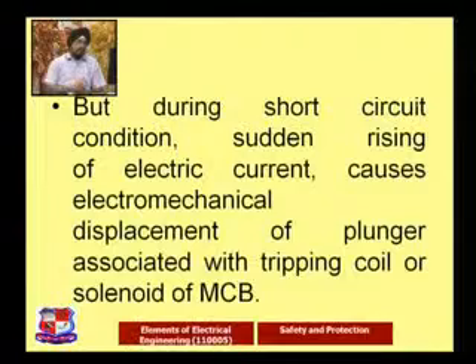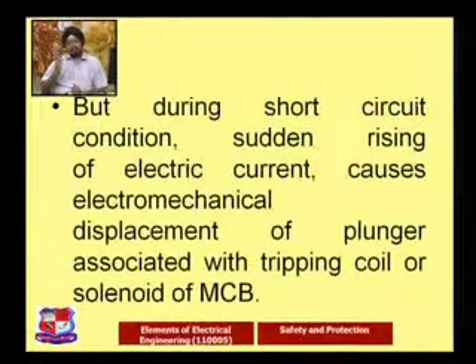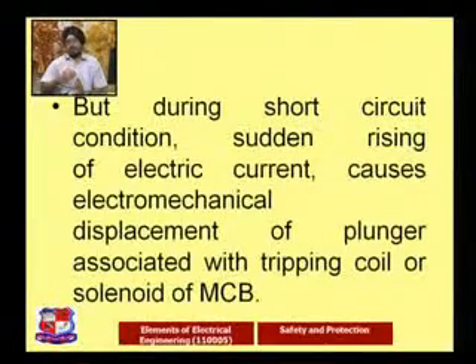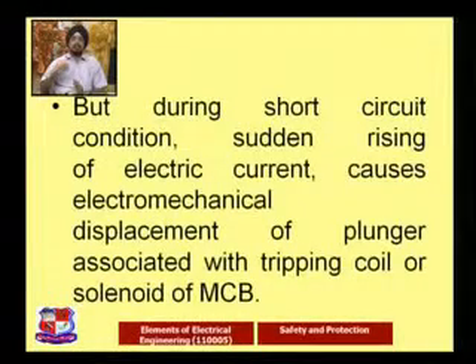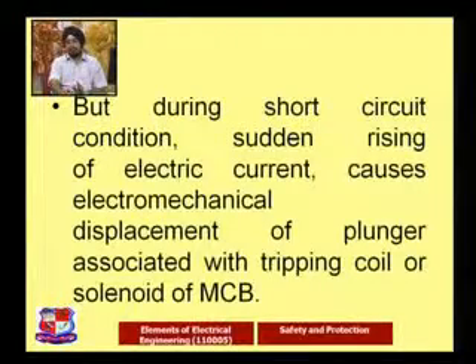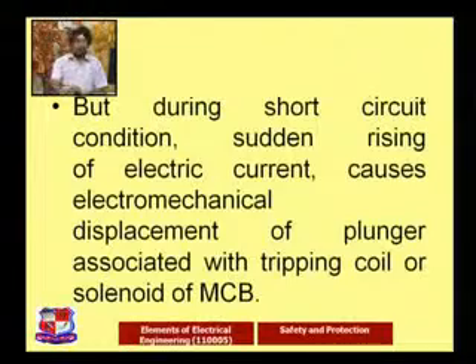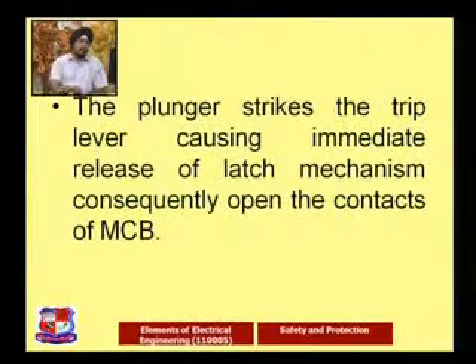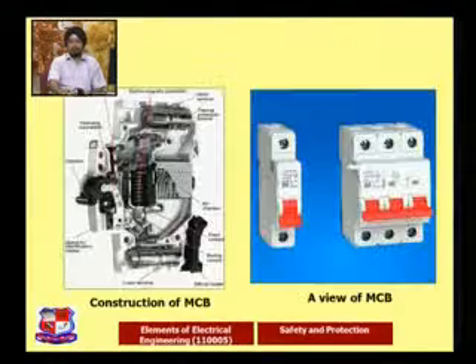And what happens during the short circuit condition? A sudden rise of current occurs, and that causes an electromechanical displacement of the plunger. So in the construction, we are able to see that the plunger is there. It will strike onto the tripping coil and give the signal to the MCB, and the MCB's contacts will come into the off position, and that is how the open circuit condition is achieved. The plunger strikes the trip lever, causing the immediate release of the latch mechanism. Consequently, it results in the opening of the contacts of the MCB, and in that manner our circuit is protected.